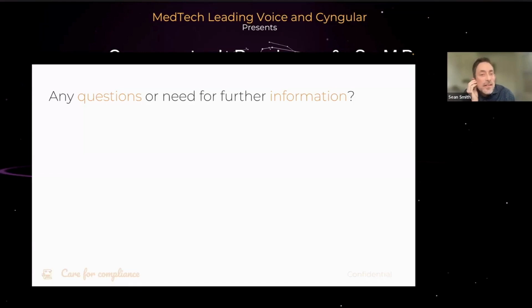Here's an interesting question. For devices submitted pre-eSTAR program, is it expected to see more scrutiny from the FDA during inspections regarding cybersecurity requirements? My expectation is that that will be the case, but how that will work out in practice remains to be seen. These are now the new requirements and they're backed up by regulations. So in that sense, the FDA inspector should be aware of these changes in regulations and should actually audit against them. So yes, I expect that, especially with the harmonization of the 81001-5-1 standard.